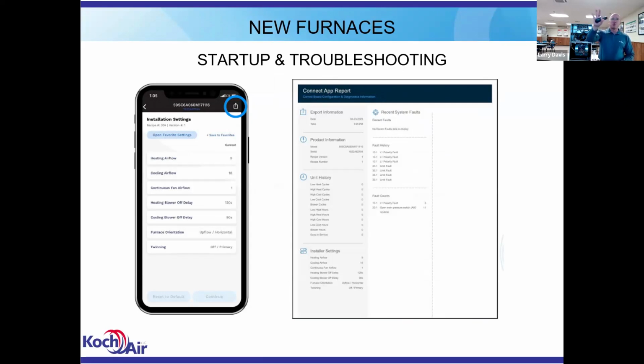You can export a report that will have all of the information: the furnace model, serial number, the date and time that you pulled that information, unit history, any history of any faults that's in there, current fault history. If there's any current fault history or any faults that have taken place within the last 72 hours, it'll display those. Fault counts: after 72 hours, it clears that out of its memory, but it counts that it hit that fault so many times. So that's a way you can track through the life of that furnace how many times you're hitting a certain fault if you keep getting a repeat fault. The unit history has all your run cycles, how many times it started, how many run hours, things like that. And then it has a list of your installer settings.